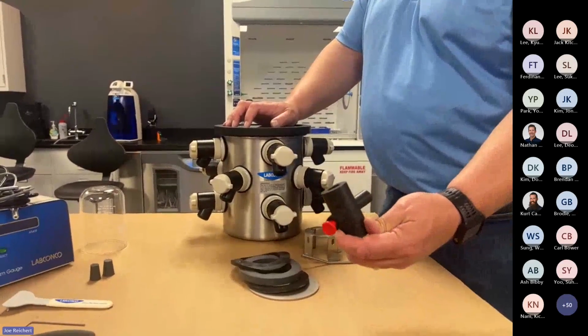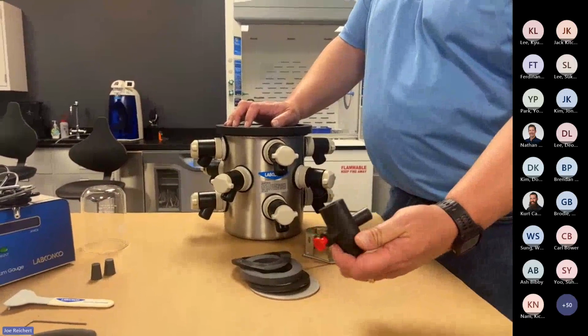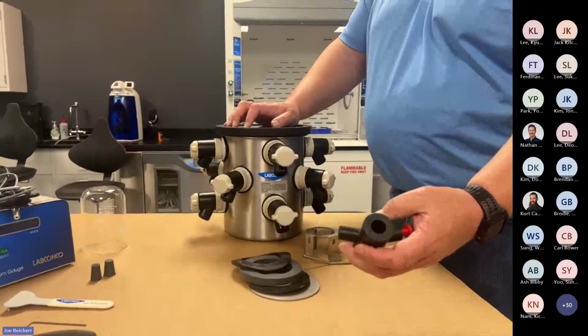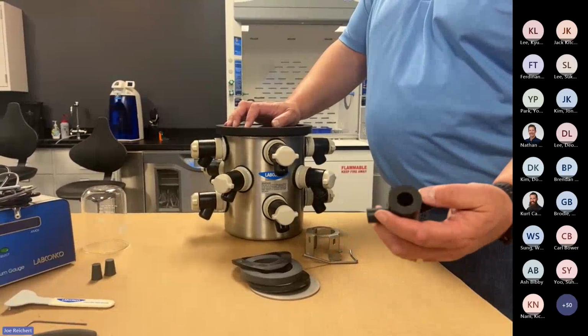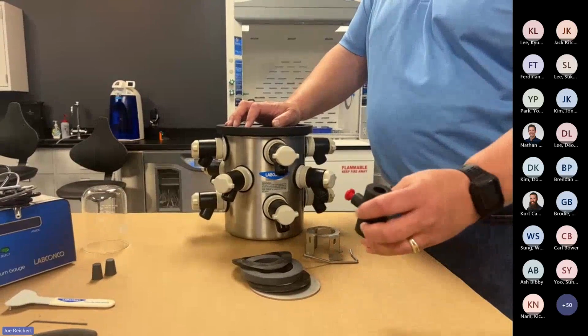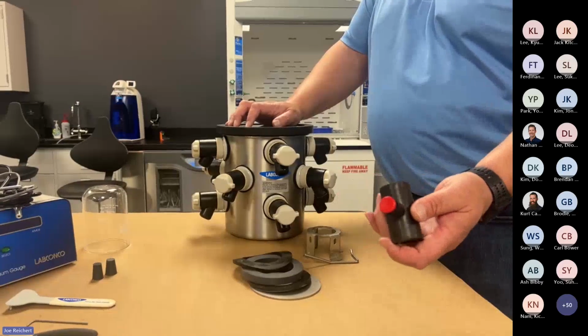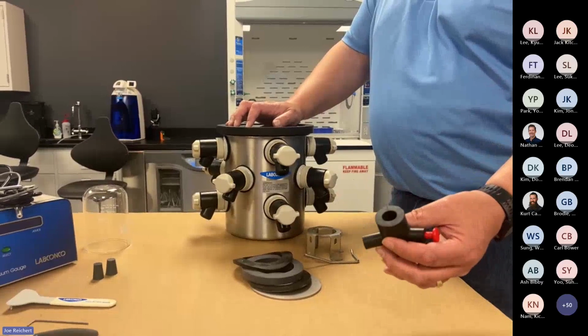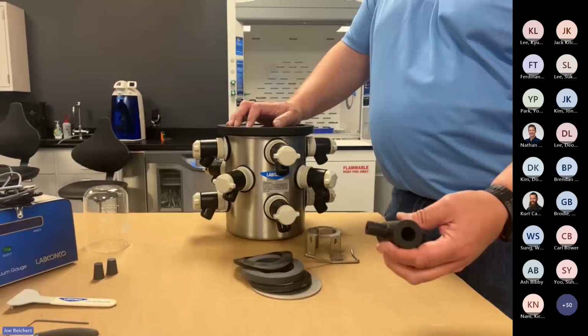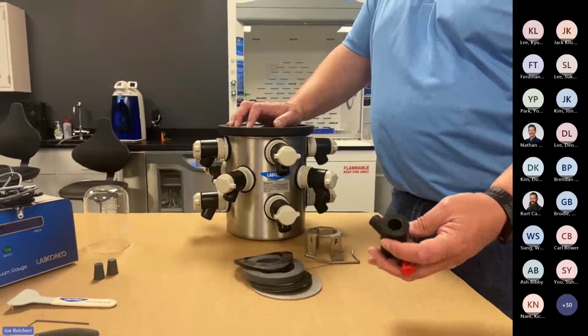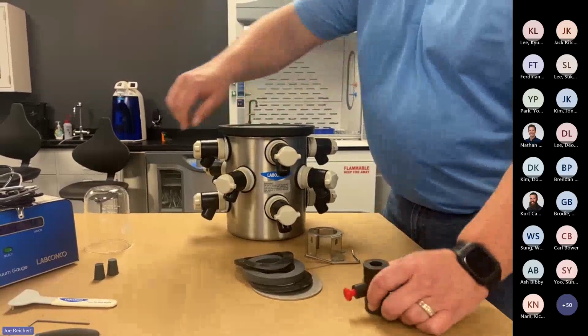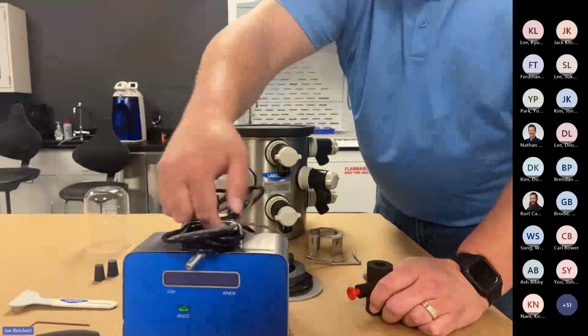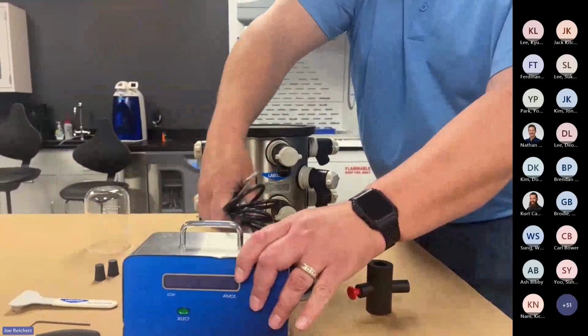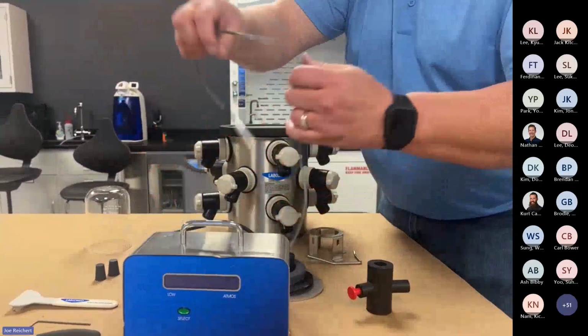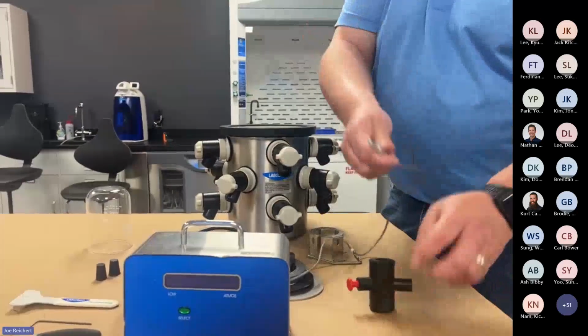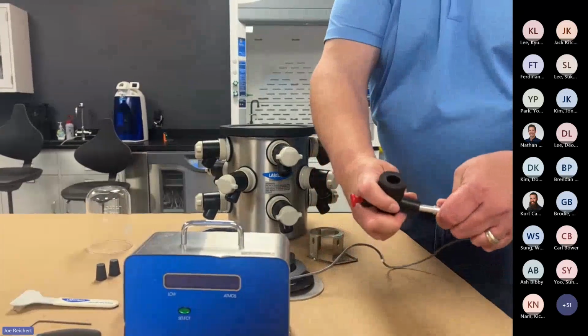It's in the very back, and we'll see it here in a moment inside the machine. This is what has your vacuum release valve, has your vacuum sensor, and it plugs into the back of the chamber in the machine. So we take these, it fits directly onto the hose barb or the hose adapter of your vacuum pump.